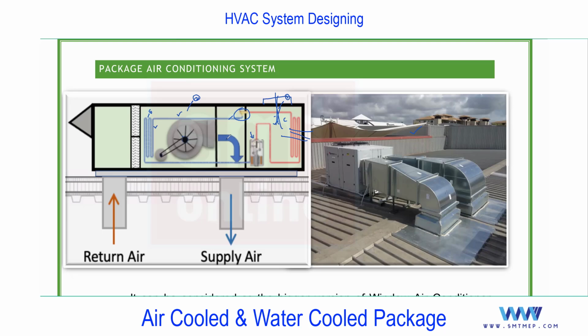Okay, so in package at the evaporator side, you'll find double skin: nothing but a cabinet, then insulation, and again inside one more cabinet. And here in this image, you can find, you see, double skin means on both sides, an insulated body with insulation. You'll find a cabinet, then insulation, then one more cabinet inside. Inside, you'll find thermocol or polyurethane completely inside. So generally, we call it double skin. So remember the term double skin means body with insulation. It can be with different units also.